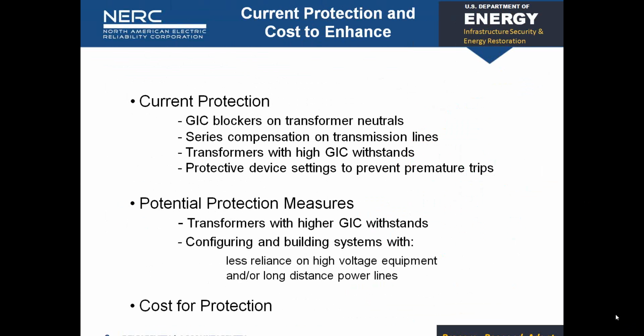In terms of protection, the things that could be put in would be actually GIC blockers -- I'm going to talk about that a little bit and what the cost is. Series compensation can go on the power lines and actually block the quasi-DC currents from coming into the transformer as well. You can put different kinds of grounding devices on your transformers, or you can design new transformers that just aren't susceptible to this.